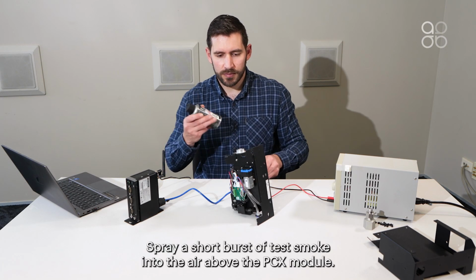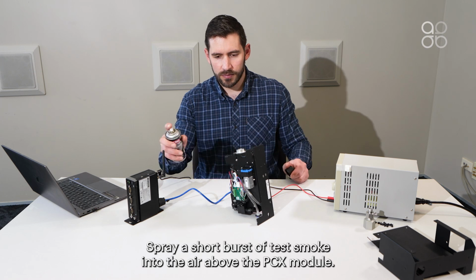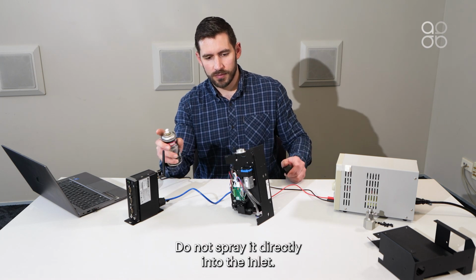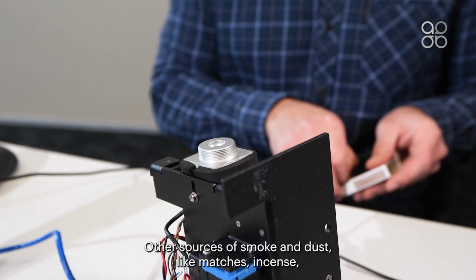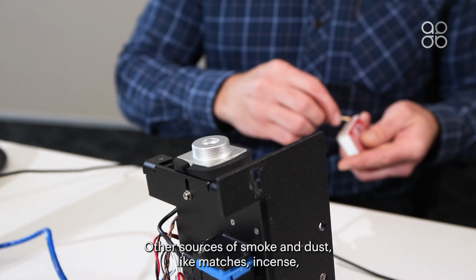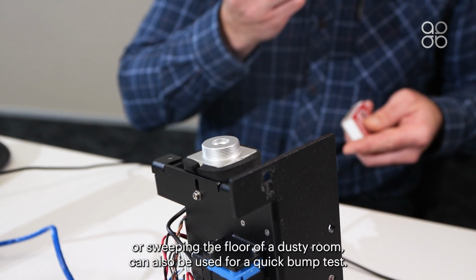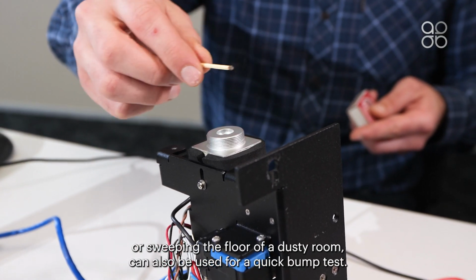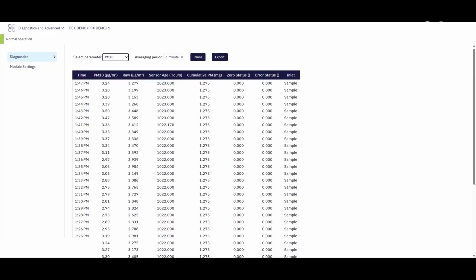Spray a short burst of test smoke into the air above the PCX module. Do not spray it directly into the inlet. Other sources of smoke and dust, like matches, incense, or sweeping the floor of a dusty room, can also be used for a quick bump test. Monitor the PM readings via Cloud or Connect and ensure they increase following the bump test.